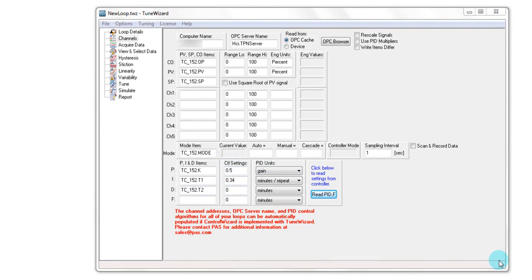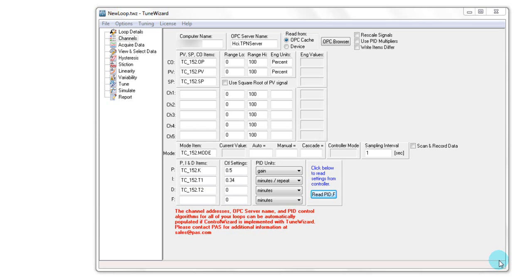Now that I have defined the OPC connection for this control loop, I can perform a number of process tests to gather data which will enable me to quantify instrumentation issues like valve hysteresis and stiction, or estimate the process non-linearity and variability. In addition, I can use process data to tune the control loop.